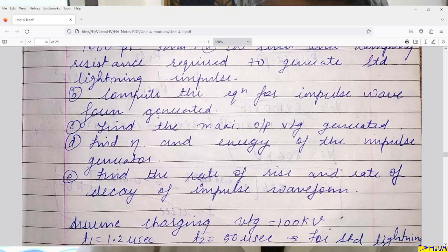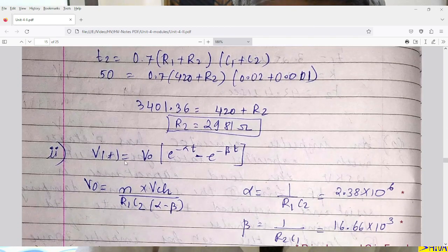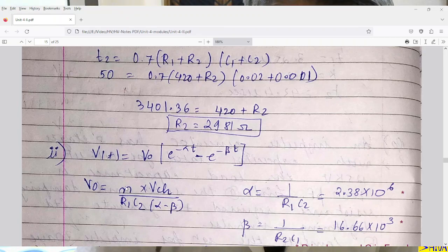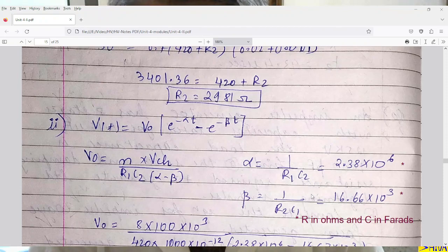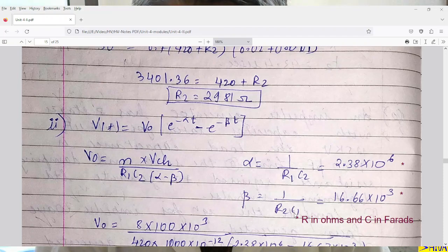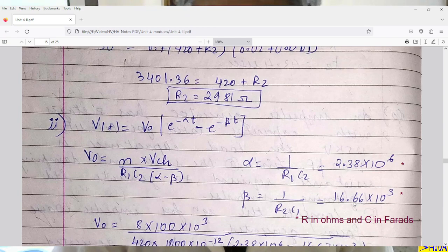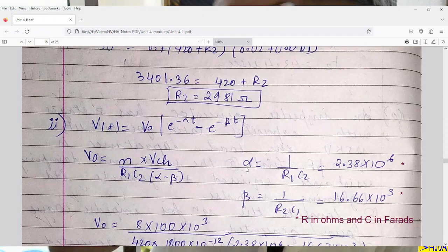The second part is to compute the equation for the impulse waveform. The equation is Vt = V0 × (e^(−α·t) − e^(−β·t)), where V0 = N × V_charging / (R1·C2·(α − β)). Here α = 1/(R1·C2) and β = 1/(R2·C1). Taking R1, R2 in ohms and C1, C2 in farads: α = 2.38 × 10⁶ and β = 16.66 × 10³. When nothing is mentioned, we use approximate equations.